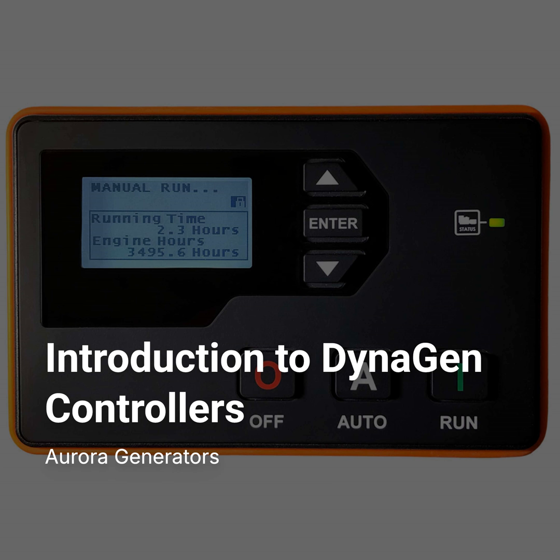Ah, clever. There's also a really useful battery recharge function. If the controller's in auto and sees the battery voltage dip below a set point, it starts the engine just to charge the battery. Exactly, it runs it for a set period to top up the battery, making sure there's always enough juice for the next auto start. Really smart for maintaining readiness.